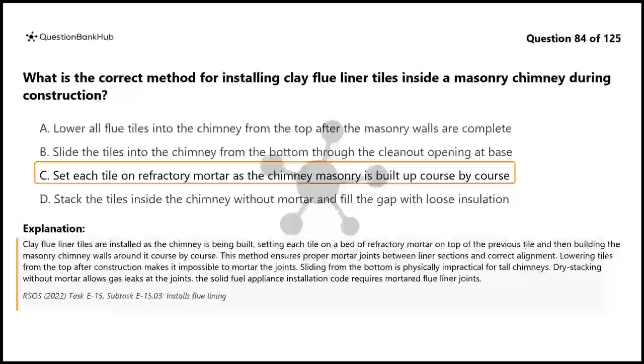Lowering tiles from the top after construction makes it impossible to mortar the joints. Sliding from the bottom is physically impractical for tall chimneys. Dry stacking without mortar allows gas leaks at the joints. The Solid Fuel Appliance Installation Code requires mortared flue liner joints.